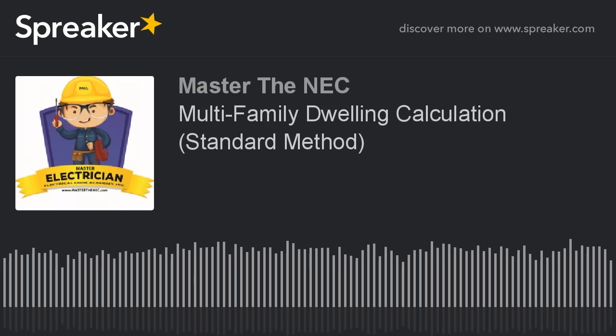That's the general receptacles that you're going to space every 6 feet and 12 feet, so that no point along the floor line is more than 6 feet from a receptacle. That's what's required in 210.52. All of those normal receptacles and all the general lighting, we're not talking about specialty lighting, we're talking about the general lighting application. All of that gets figured in here and applied to this demand factor.